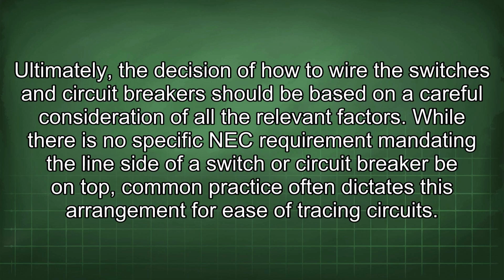Ultimately, the decision of how to wire the switches and circuit breakers should be based on a careful consideration of all the relevant factors. While there is no specific NEC requirement mandating the line side of a switch or circuit breaker be on top, common practice often dictates this arrangement for ease of tracing circuits.